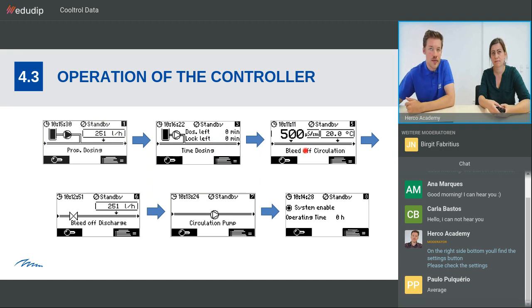On the right side, you see the bleed off information. So basically the temperature and the conductivity, and also what you're actually doing, so circulation, or if you're taking water out of the system. In the next one, you see the information about the bleed off discharge. Again, you see the valve, and then you see the flow that's actually going to the drain that is also logged. So you know how much water you have wasted.